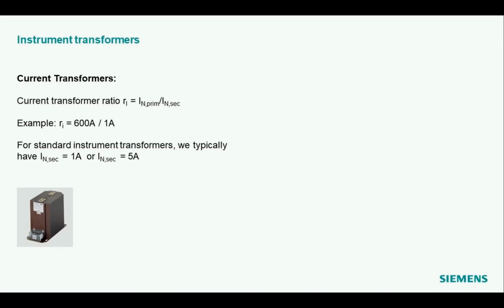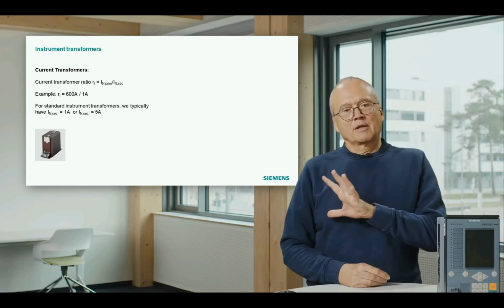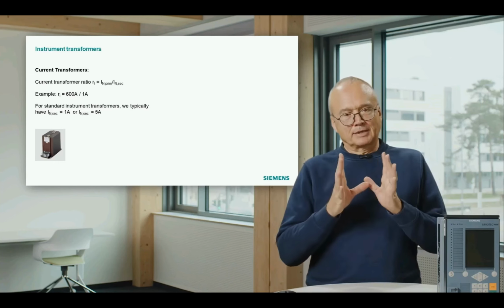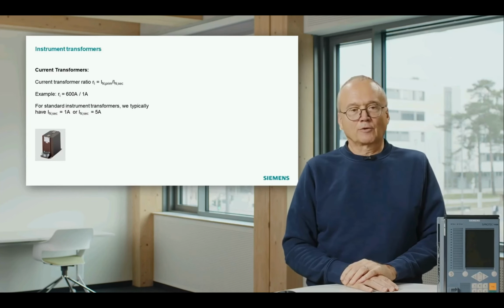Just to illustrate that a little bit, I want to come back to the current transformers. You see here again a picture of a current transformer for distribution level. In this case, it has a current transformer ratio of 600 amp to 1 amp. That means the primary rated current is 600 amps. On the secondary side, we have 1 amp, and that is what goes into the protection relays. And in protection, traditionally, we have 2 standard nominal currents on the secondary side, and that is either 1 amp or 5 amp for this conventional type of transformers. There are other types also coming up, but still the big majority has these current transformers.